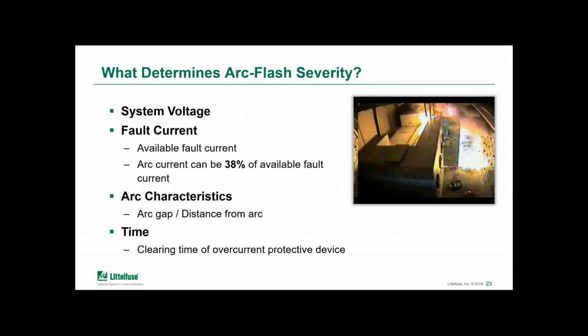And that's a function of the size of the transformer or generator supplying power. And the current is limited by the impedance of the system and also the characteristics of the arc itself, including the arc impedance, or the fault impedance, I should say. So the bigger gap between bus bars would mean less current if we hold all other variables the same. And the distance that an object or person might be from that arc would also determine what amount of heat is transferred to them. So these factors can certainly be tweaked at the design phase, but they're a little bit more difficult to change after the fact.